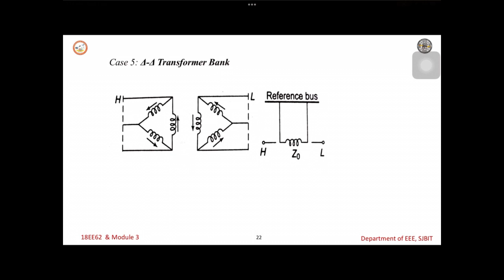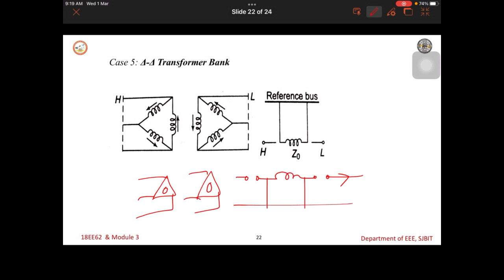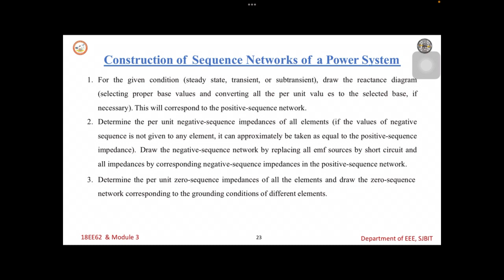Next, we will see how to write the zero sequence network for delta delta. Delta delta. So, here 3-phase 3-wire, here also 3-phase 3-wire. So, here there is a provision of current to flow in the phases. Therefore, delta means you always write open circuit, but it carries current in the phases, not in the lines, for zero sequence current. This is the equivalent circuit for the delta delta connected transformer bank. Next, we will see the construction of the sequence network of the given system.